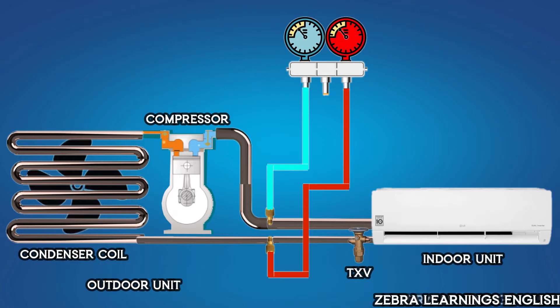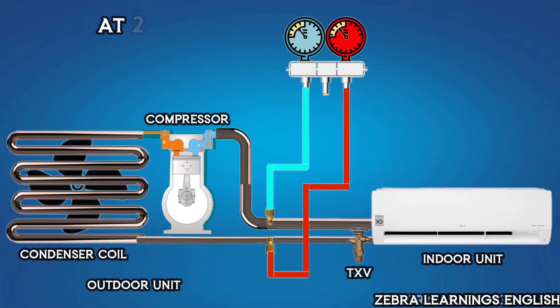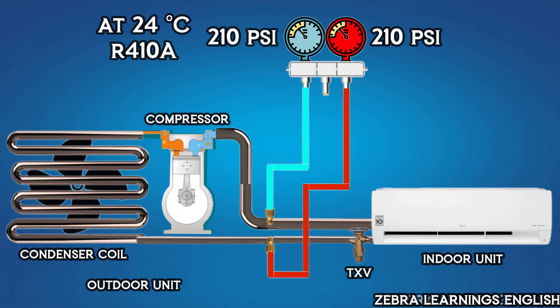When the AC unit is off, the refrigerant pressure is equal on its low-pressure side and high-pressure side. For example, at 24 degrees Celsius, when our R-410A unit is off, the refrigerant pressure on both the low- and high-pressure side is 210 PSI. When the temperature increases, the pressure of the refrigerant also increases. The pressure of the refrigerant at 27 degrees Celsius is 236 PSI.